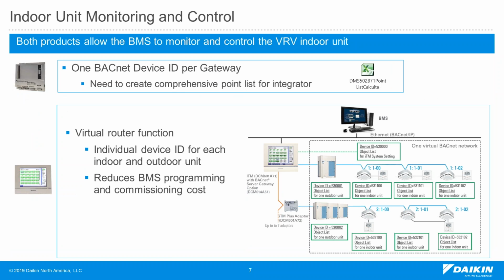Another difference between these two products is the virtual BACnet router function. The hardware gateway can only provide one device ID per gateway, which means that you need to provide a comprehensive point list to the integrator for them to understand which BACnet objects apply to which indoor unit. And the ITM gateway, on the other hand, has a virtual BACnet router function. With this function, you can assign an individual device ID to each indoor and outdoor unit. It can help reduce the programming time because the integrator can easily copy-paste his program from one indoor unit to another, and just need to change the device ID instead of changing the BACnet instance number for each individual point.